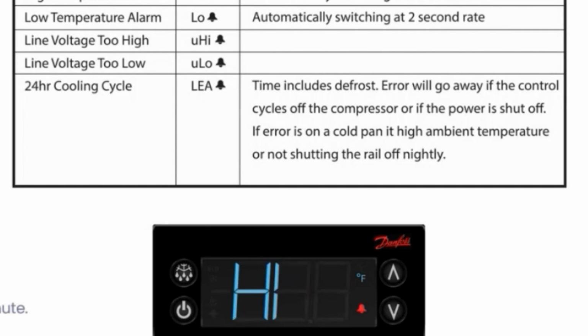What the real-time probe reading is going to do is allow us to see what those particular probes are reading at that second. So we would go in and check the air probe. More often than not, if we had an issue with the air probe, a lot of times they'll read erratically, and we'll see it on the display without having to go into the programming for that. But I'll still have you check that quick, because again, it literally takes a few seconds to do that. From there, I'll have you go over and we'll check the evaporator sensor.